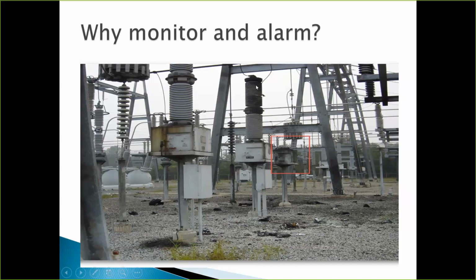It shot the porcelain insulator that houses the capacitors. This is about a 50-yard debris field. You can see where it was on fire. It caused some burning, very catastrophic failure. And this, guys and girls, if you think about it, anytime you have a failure of this device, it causes your bulk electric system to have an operation, okay? That's going to impact your customers, your power quality, your CMI, and if you notice that it threw shrapnel everywhere, it could potentially damage other equipment, okay?